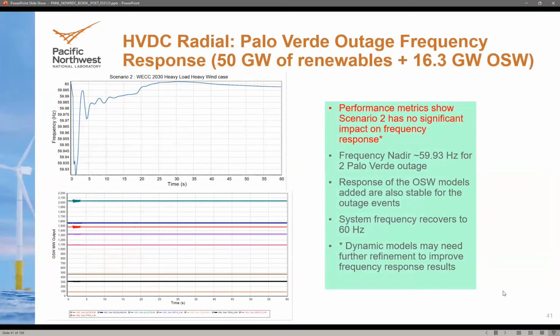Going forward to the HVDC radial, we see a similar response and not a significantly worse frequency nadir, with the performance metrics for frequency response also within the limits for WECC standards. We also observed the responses and megawatt output of the offshore wind plants following the Palo Verde outage. We see some minor oscillations on some of them, but otherwise they are pretty much flat and stable in their performance from the offshore wind resources.